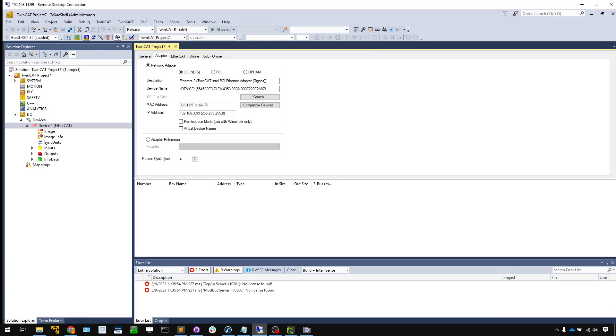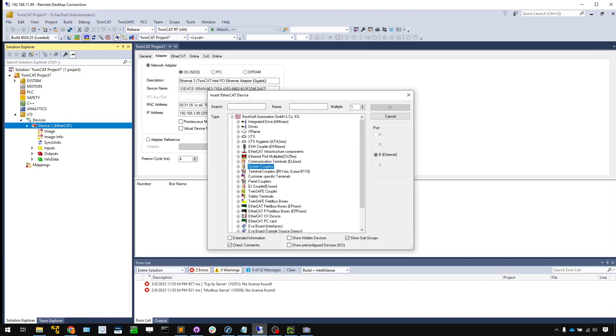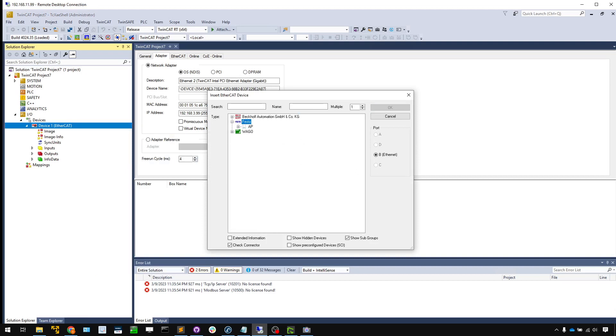The next step is to insert our Festo EtherCAT slave. You can scan for devices, but sometimes it cannot find all modules, so the best way is to add them manually one by one. It takes some time but gives you 100% accurate configuration. Right-click the EtherCAT master, add new item, find Festo in the list. In our case we are using the CPX API ECM M12 — select it and press OK.